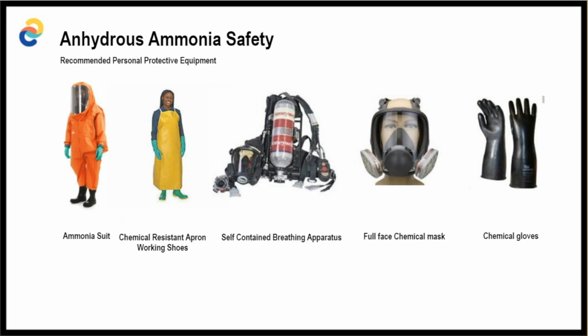Availability of personal protective equipment should be at site: an ammonia suit, chemical resistant apron, self-contained breathing apparatus or SCBA, full face chemical mask, and chemical gloves. Depending on the size of the plant, we recommend a minimum of 2 units of SCBA and a full face mask. Also, during activities, we recommend a two-person buddy system should there be any handling activities for ammonia.